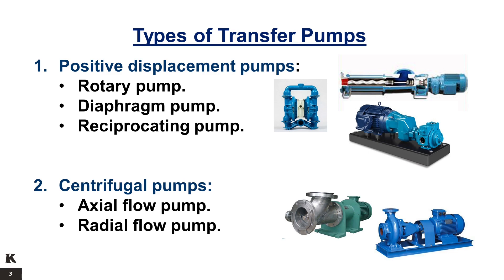The main disadvantages of a positive displacement pump versus a centrifugal pump are that dry running can be catastrophic due to either close clearances of parts, or in the case of progressive cavity pumps, the interference fit between the rotor and stator. All positive displacement pumps require the installation of a pressure relief valve to prevent failure of the pump or piping in case of accidental closure of the delivery valve or blockage in the piping. Most positive displacement pumps will also produce pulsations which can lead to undesirable effects like vibration, product damage, and water hammer. Positive displacement pumps also have a limited flow rate range compared to centrifugal pumps.